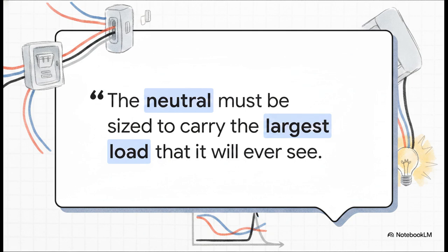Finally, as you calculate the loads for all these phases, do not forget the neutral. Section 220.61(A) dictates that the feeder neutral load is the maximum unbalance between the neutral and the largest load connected to any one phase. Essentially, neutral conductors don't care about perfectly balanced loads. They only care about worst-case scenarios, like when loads on the other phase are completely shut off.